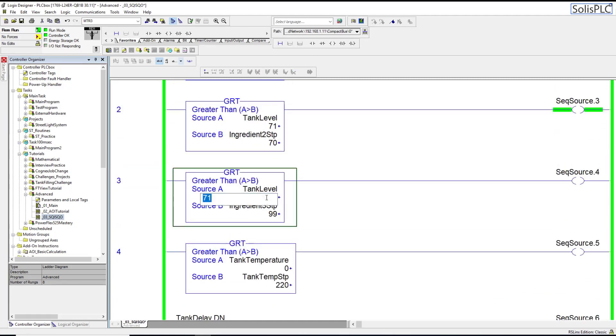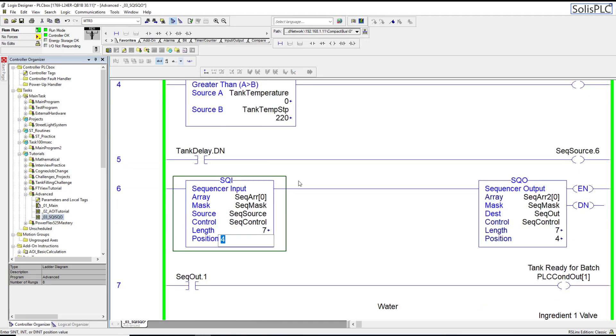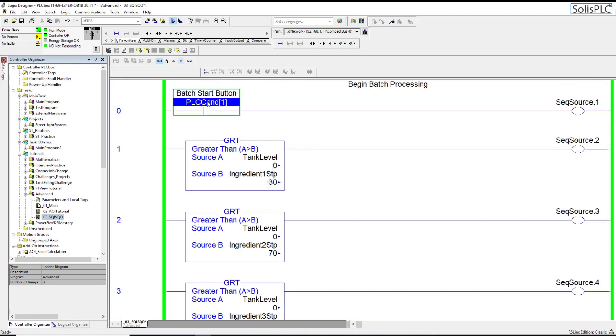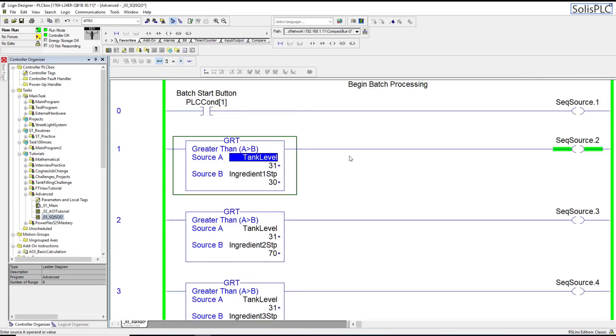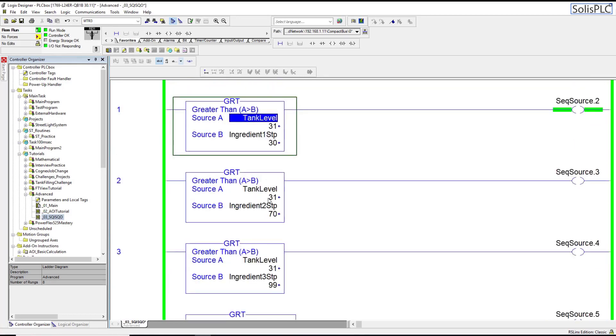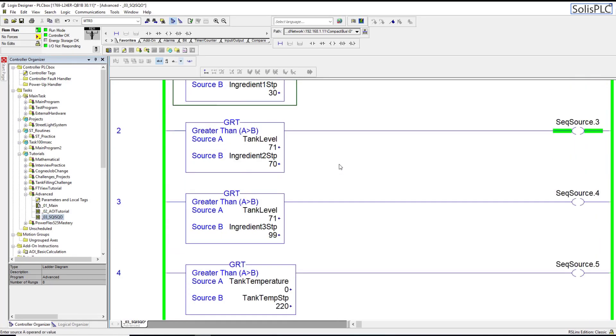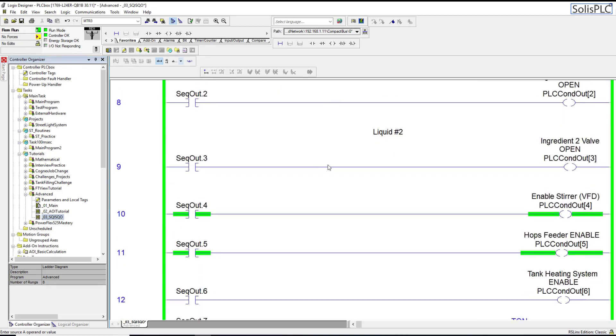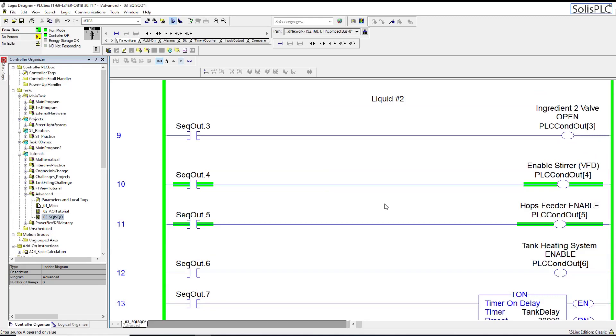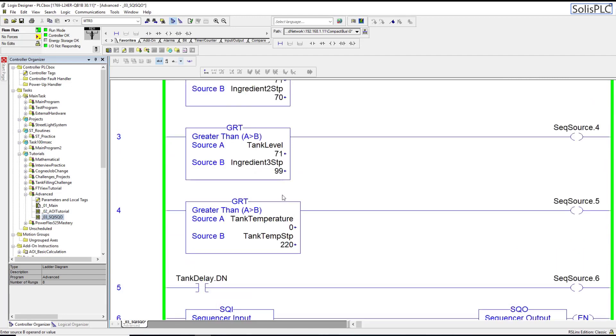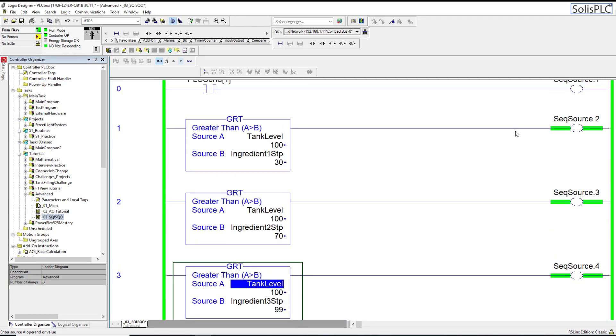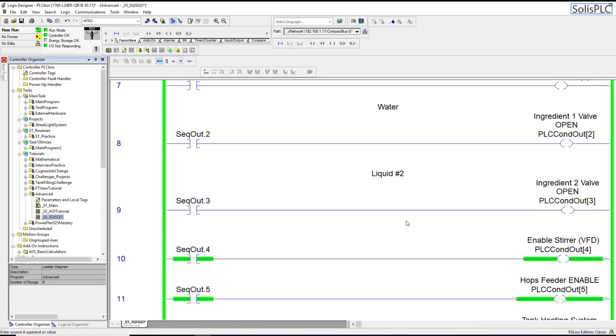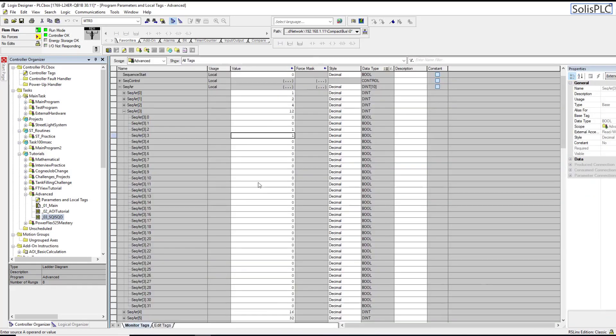Let's go back, set the tank to zero - I want to do a couple of tests since we've added quite a few functionalities. Now we are definitely opening the valve, this becomes 31 which is good, we're in step three. Now we need to go into step four - that definitely works, we're looking for both conditions. We're stirring as well as allowing the hop feeder to be inputted into the tank. The next thing we're looking for is to reach the 100 percent level.